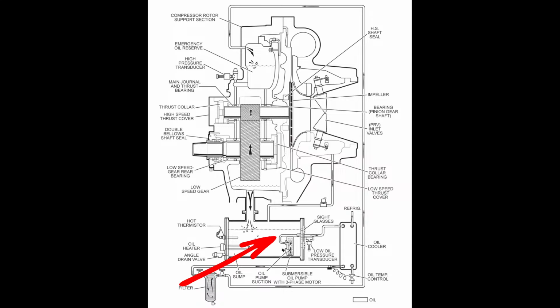Another way to do that would be getting a surface temperature down lower on the sump. So not as big of a fan of that, but that is possible. You can get your temperature down here on the shell housing. Now this is not insulated, and keep in mind it's not going to be perfect. That's part of the tricky part of taking these measurements. They're not going to be perfect to the actual thermistor, but we're trying to see, are they even in the same ballpark in the first place? So that's one of the first things I'd want to do: is my temp sensor even working correctly?